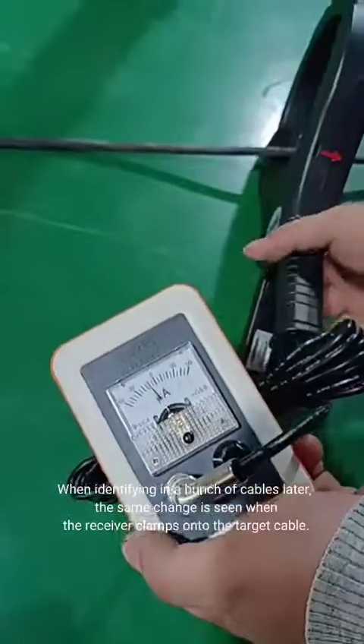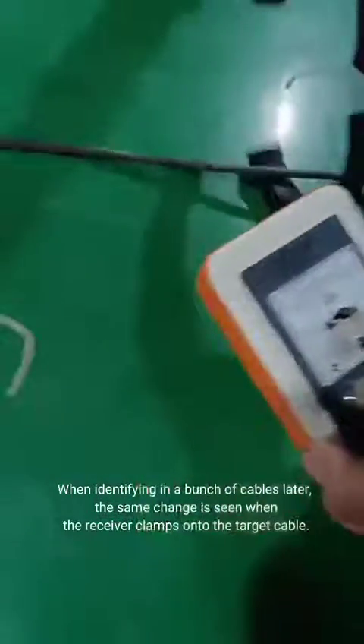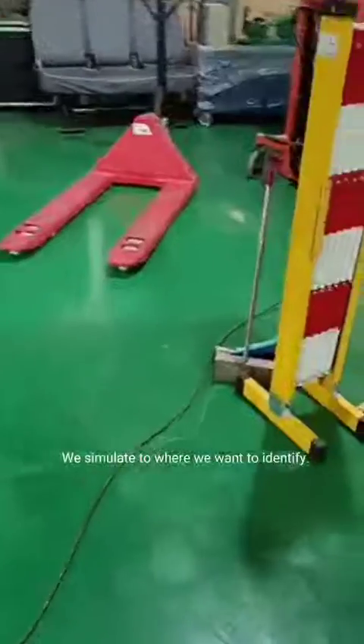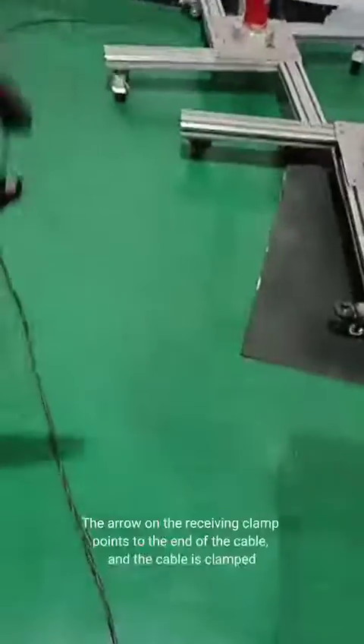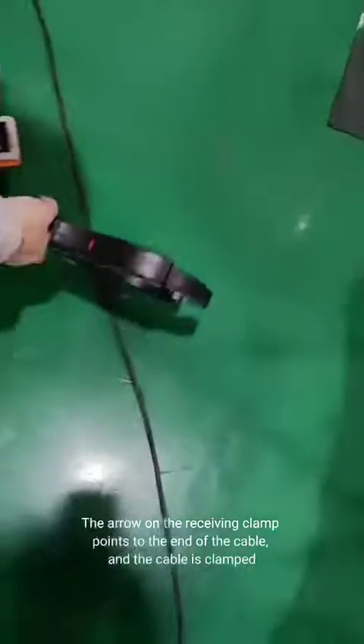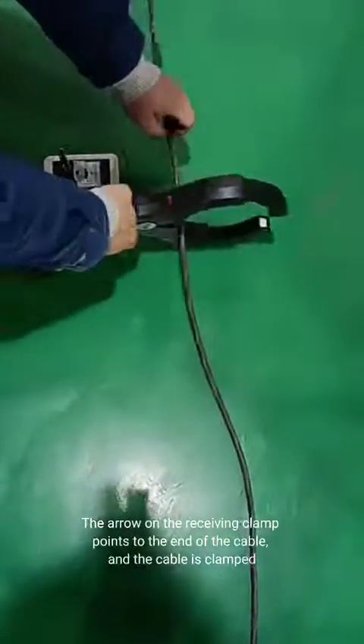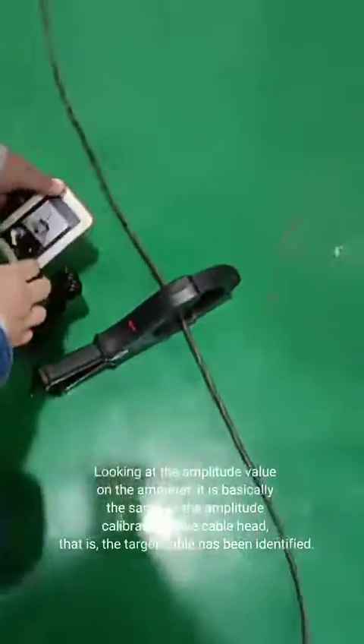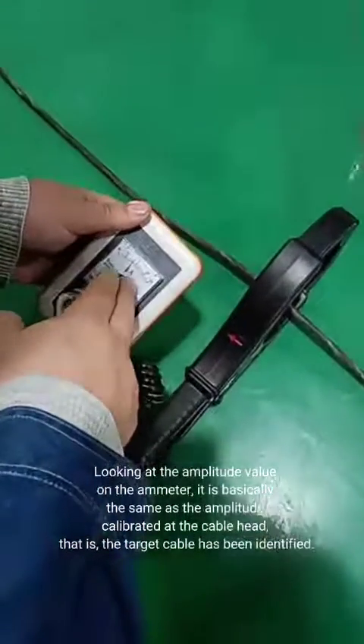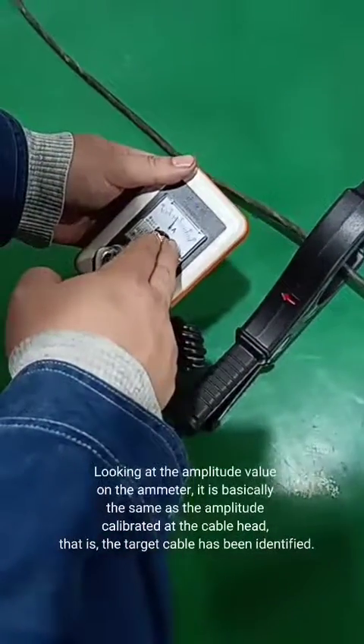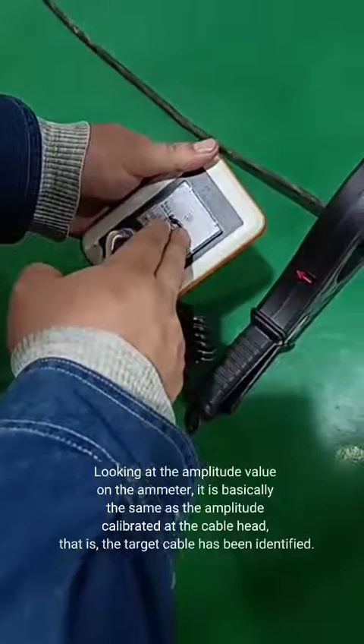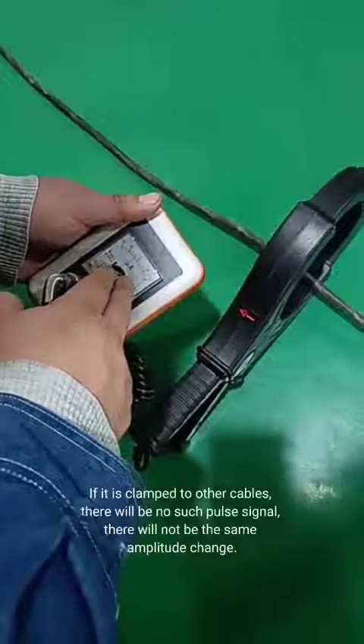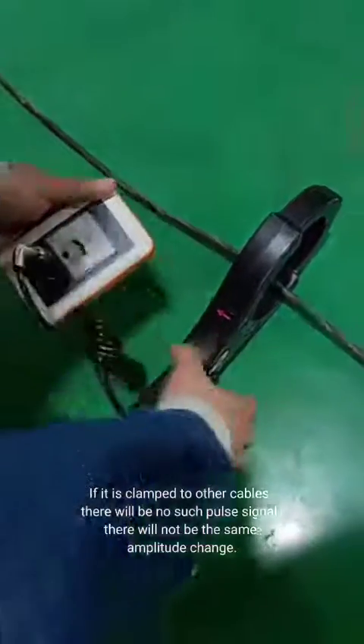When identifying in a bunch of cables later, the same change is seen when the receiver clamps onto the target cable. We simulate to where we want to identify. The arrow on the receiving clamp points to the end of the cable, and the cable is clamped. Looking at the amplitude value on the ammeter, it is basically the same as the amplitude calibrated at the cable head. That is, the target cable has been identified. If it is clamped to other cables, there will be no such pulse signal. There will not be the same amplitude change.